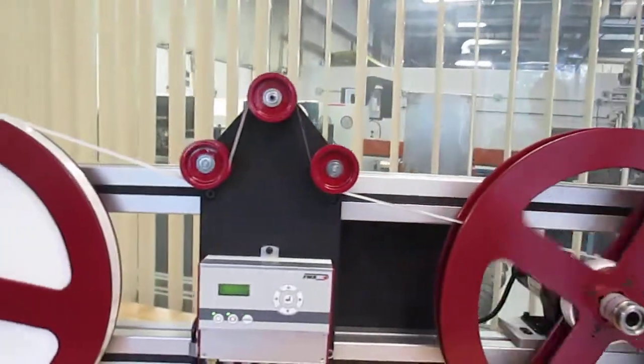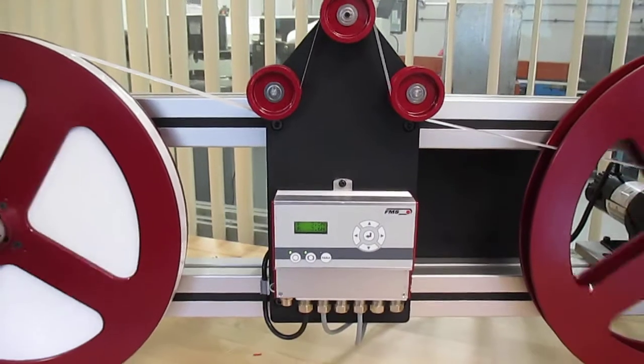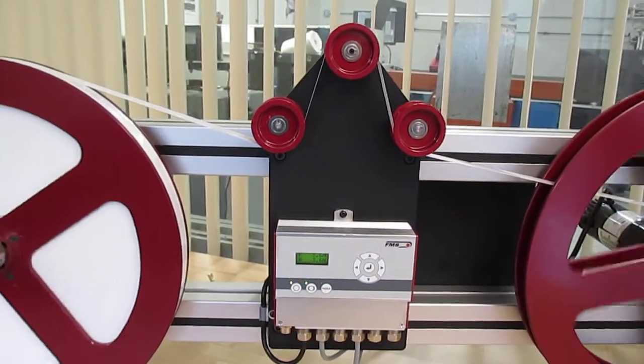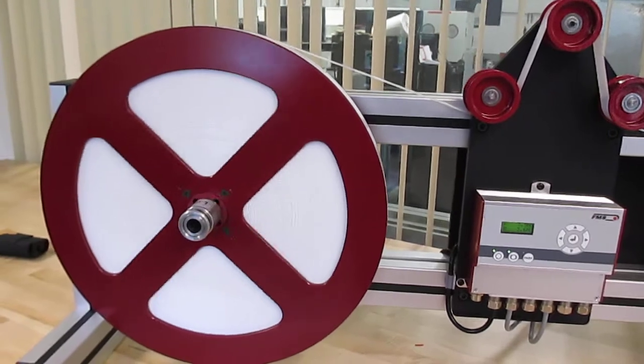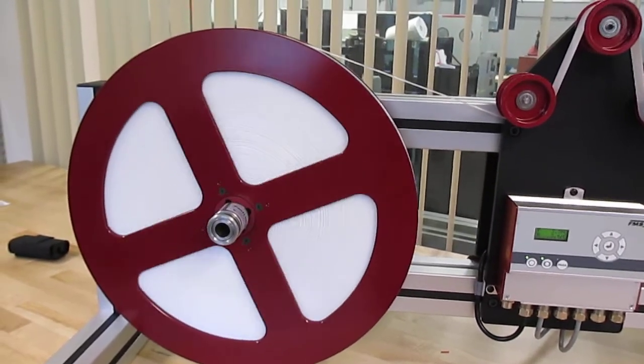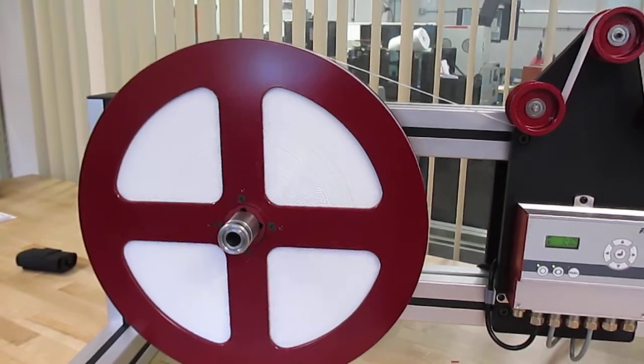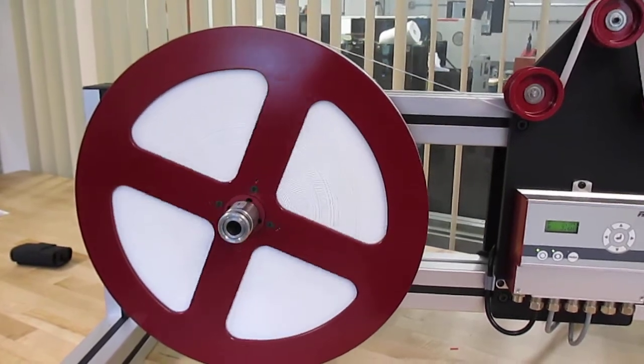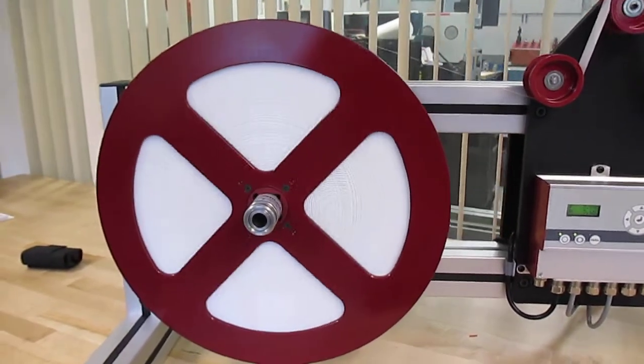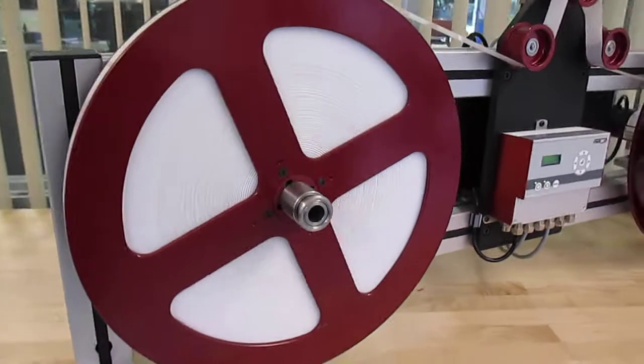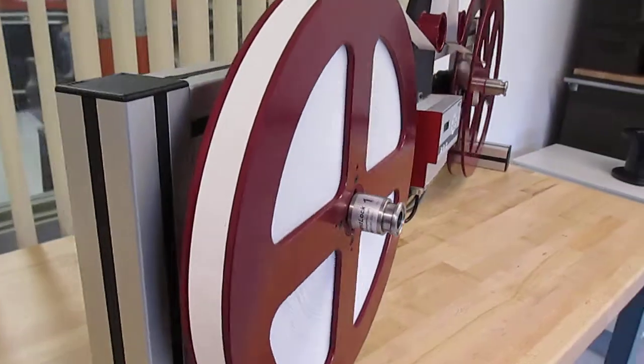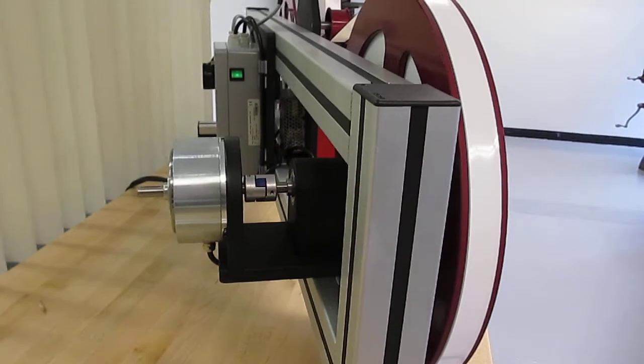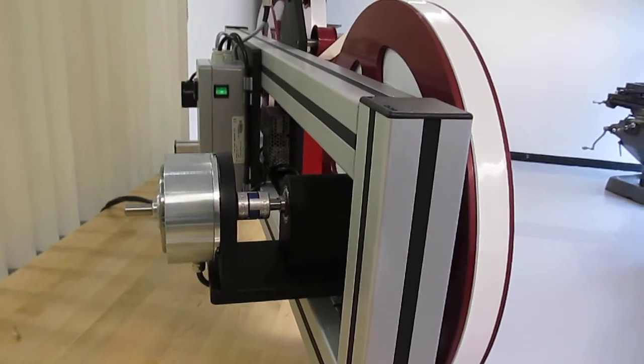It's important to use a tension amplifier in a system like this where the diameter of the takeoff payoff spool changes from 18 inches down to 3 inches. In a constant torque type of brake without feedback, the tension will increase by a factor of 6 times.